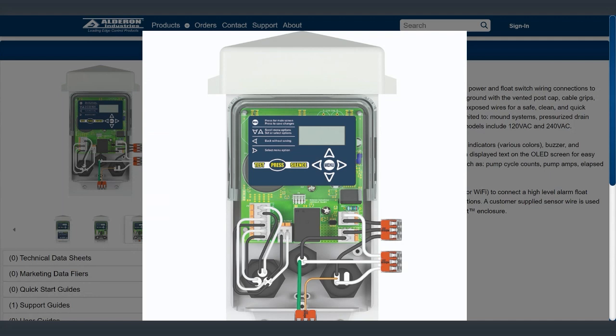So our power post monitoring series, as well as our baseline one, has inputs for high level float alarm and also a filter switch. So here's a filter switch, which you just drop in your filter if you use filters in this area. And then if the filter gets clogged up, the liquid level rises. There's a little float in here that rises up and makes a connection, and it'll give you an alarm saying, hey, come out and clean your filter off, homeowner.